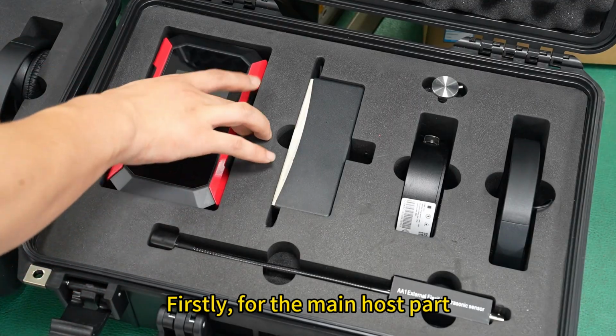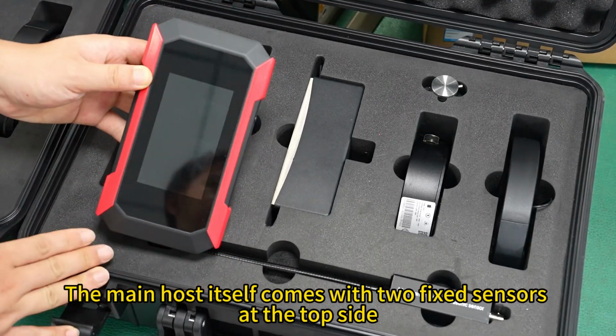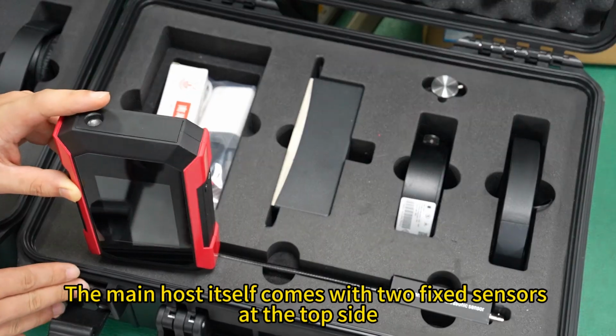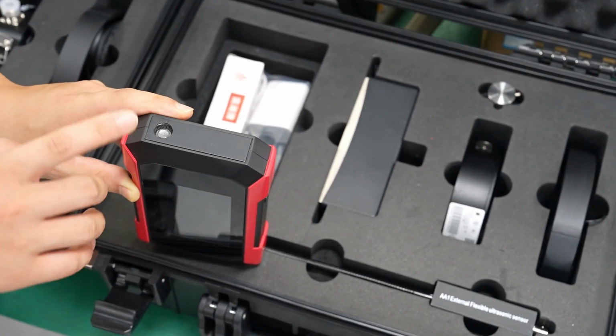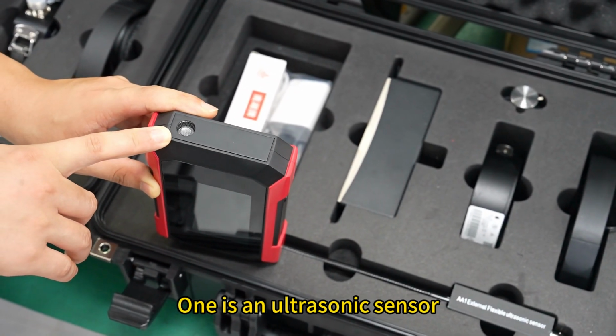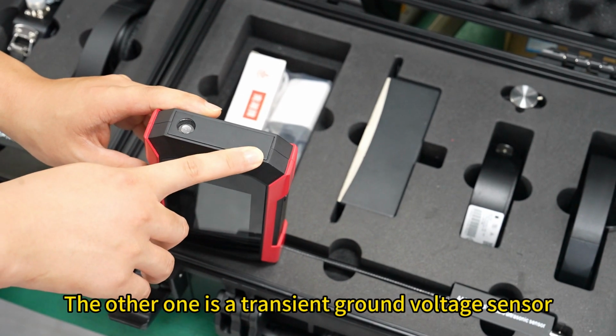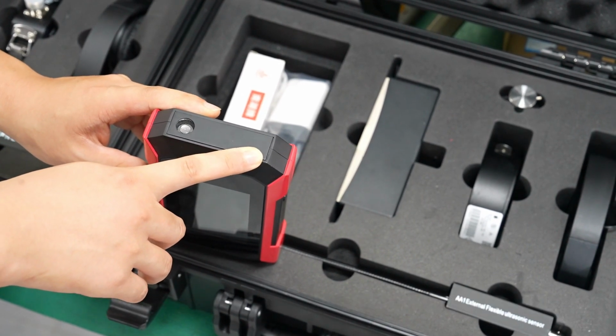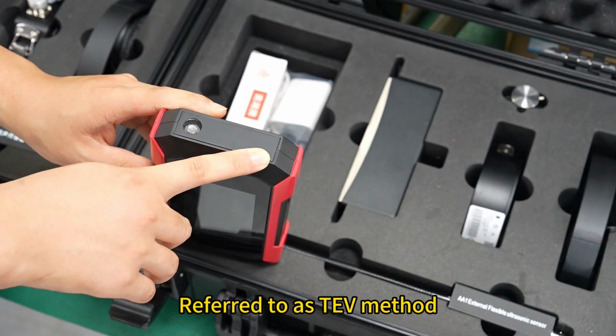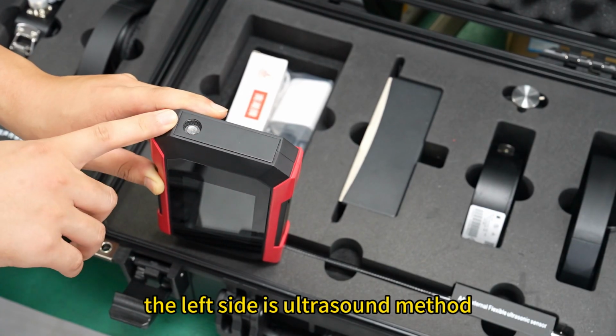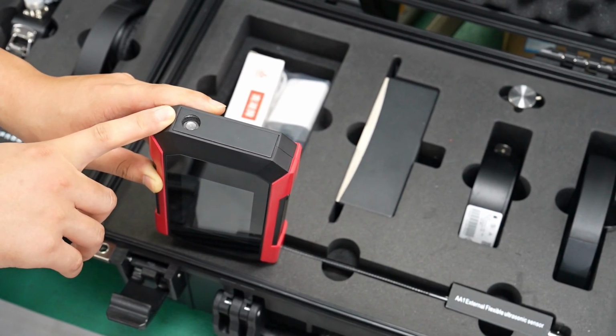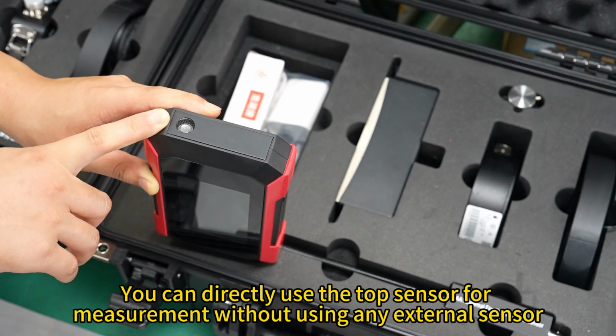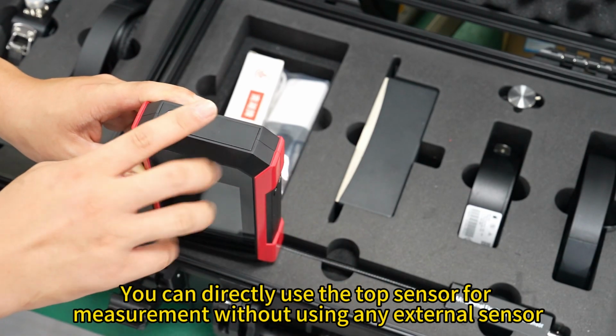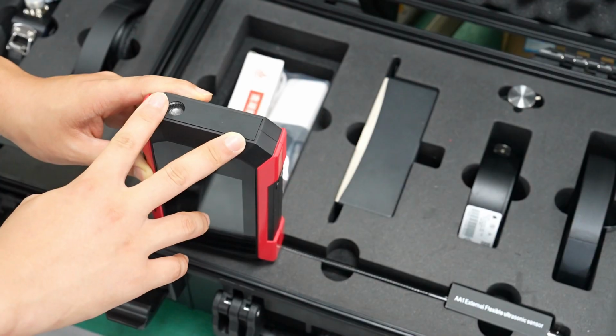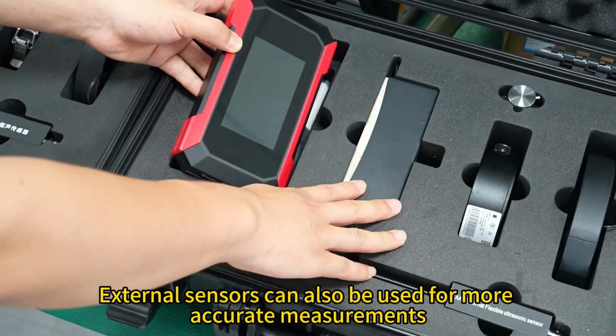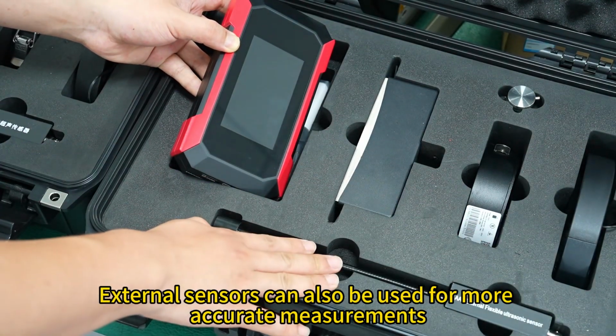Firstly, for the main host part. The main host itself comes with two fixed sensors at the top side. One is an ultrasonic sensor. The other one is a transient earth voltage sensor, referred to as the TEV method. The left side is the ultrasound method. You can directly use the top sensor for measurement without using any external sensor. External sensors can also be used for more accurate measurements.